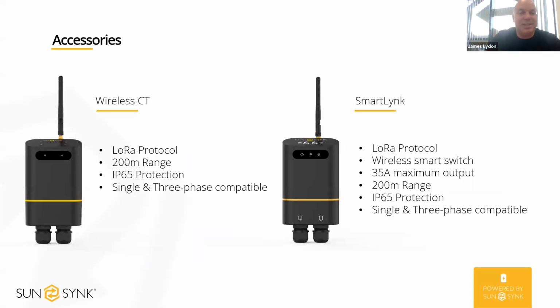Accessories, so the wireless CT. You can see this is what's going to go at your incomer. It comes with the CTs needed to go around, whether it's single phase or three phase. LoRa protocol, up to 200 meters. It's fully IP65, and the unit will work with both single phase and three phase supplies.